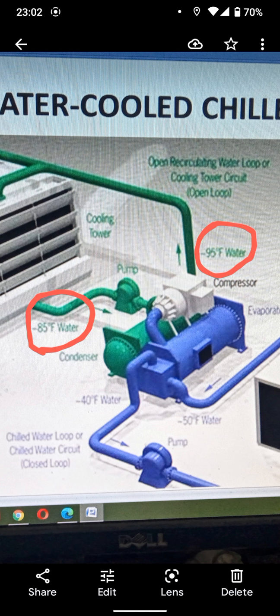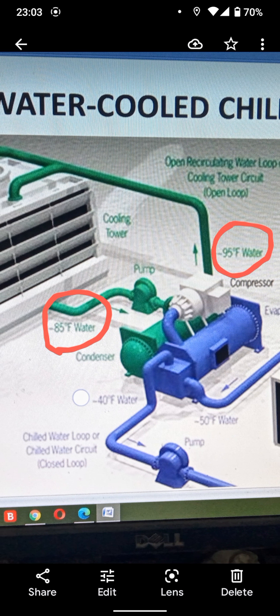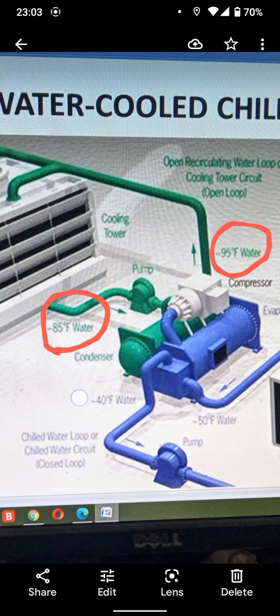First of all, we opened the condenser line on the condenser side. They have fixed an automatic water regulating valve, which is a spring loaded valve. When condenser water pressure increases, it pushes the regulating valve, and the valve is opened by spring tension, and water flows in the condenser. We removed this spring valve so that water goes to the condenser without restriction. We removed all 4 regulating valves, spring and valve. So now there is a direct hole, and water goes directly without restriction. With this removal of the automatic water pressure regulating valve, pressure is dropped, but no problem, water volume is increased in the condenser.